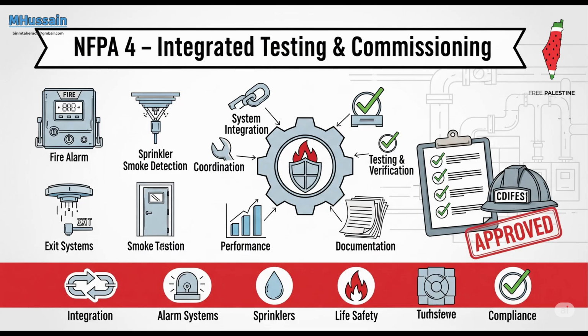This is where it gets interesting. Let's say an individual system component fails, like the main fire alarm panel has an issue during the integrated test. Okay. That individual system, the fire alarm panel, is allowed to be repaired and then retested without necessarily triggering a complete new integrated test of all the other systems again. That sounds practical. Avoids massive disruption if just one part hiccups. It is practical, but, and this is key, you do have to retest the specific integrated functions that were affected by that failure or the repair. So you test the connections again, make sure the fix didn't break something else in the interaction. Exactly. You have to confirm that specific part of the symphony is back in harmony after the repair.